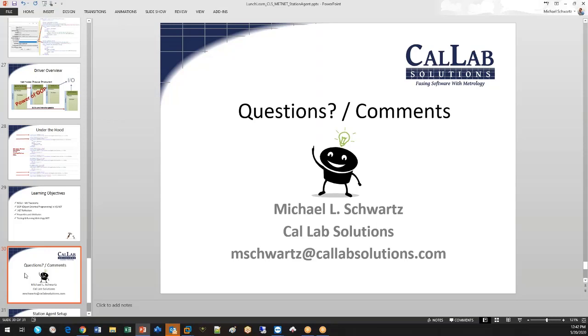Yeah, what I've been doing is, say for instance, on the station that I use to calibrate calibrators, I'll keep what I call a stable version of it going. And if I see that there are new drivers updated, I'll grab a laptop computer or something and set up a beta test station agent on that one to try it out. That way, in case a rush job comes through the door, I can go back to the stable version and use that.